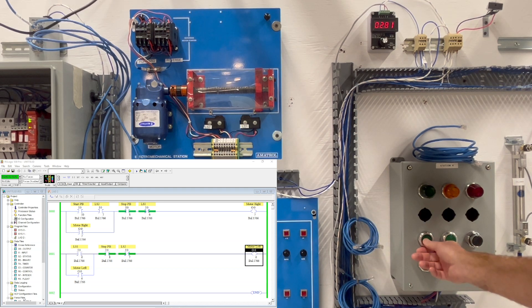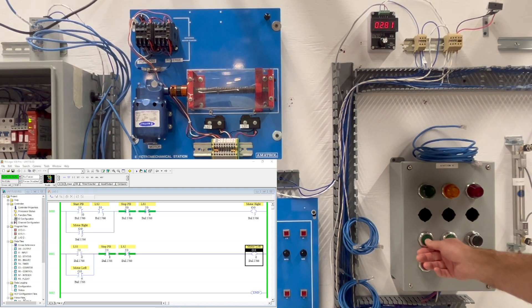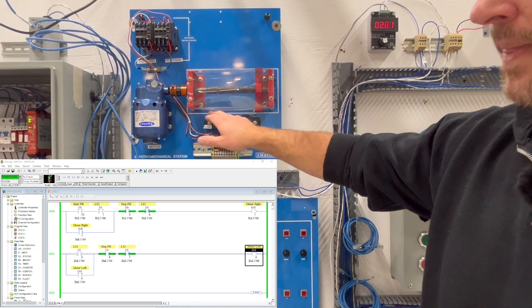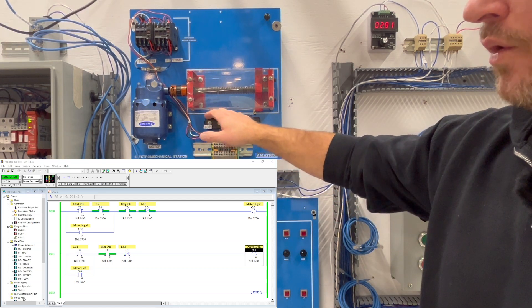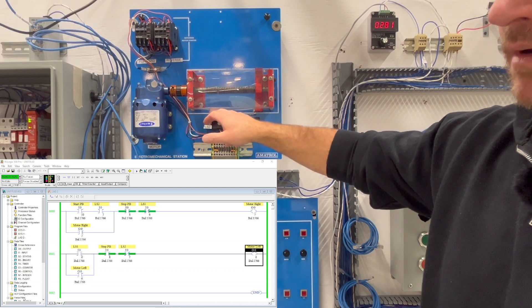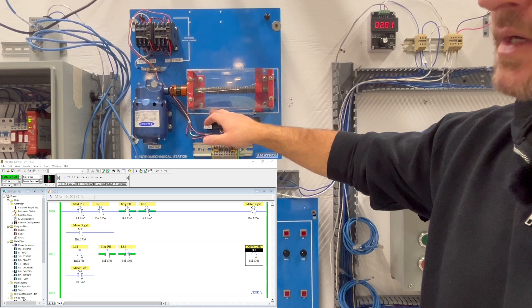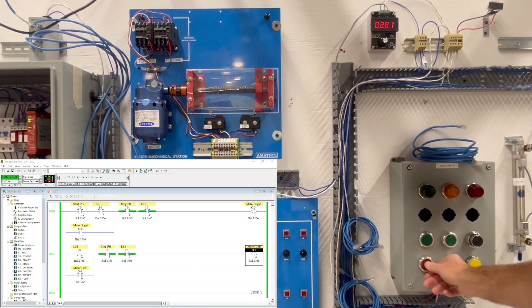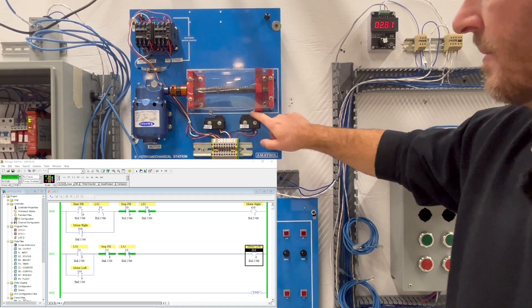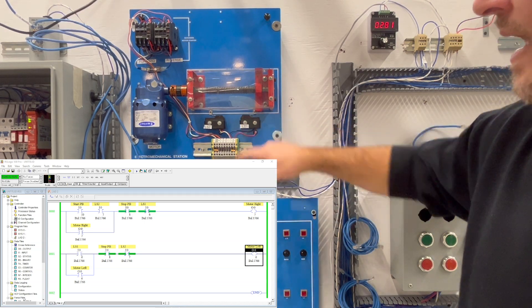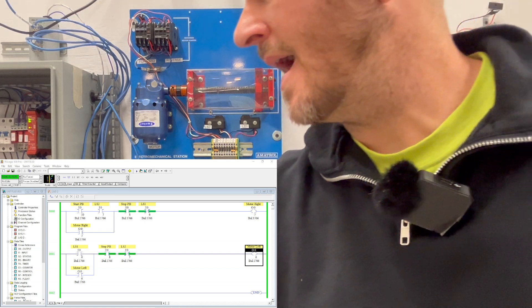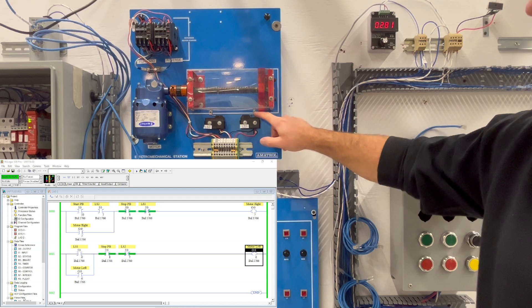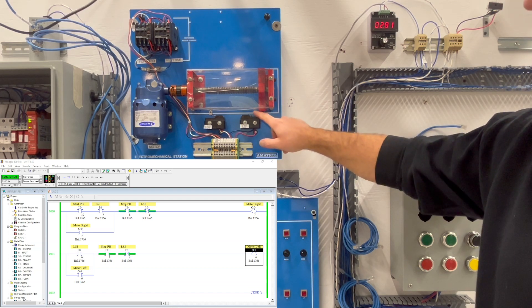So I can see here my start button is activated. I'm going to come here, activate LS2. I can see that that is getting a signal on both rung zero and rung one. My stop button's activating okay. Let's come here to LS1. Okay, LS1 is not activating on my screen on rung zero or one.